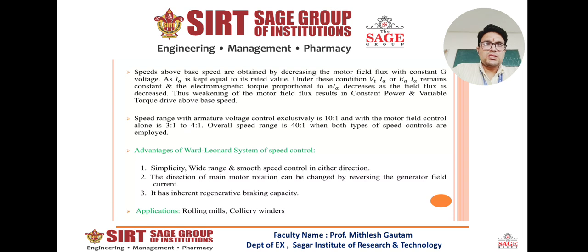There are some advantages and applications of the Ward-Leonard system. Simplicity, wide range, and smooth speed in either direction. The direction of main motor rotation can be changed by reversing the generator field current. It has inherent regenerative braking capacity, and its applications are rolling mills and colliery winders.